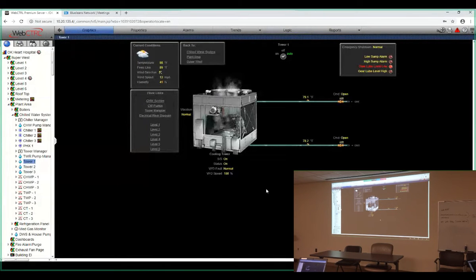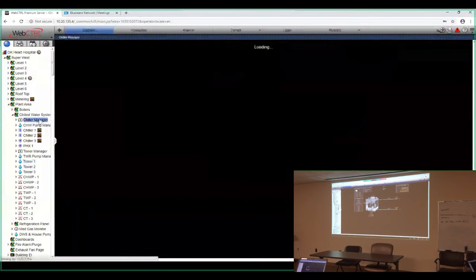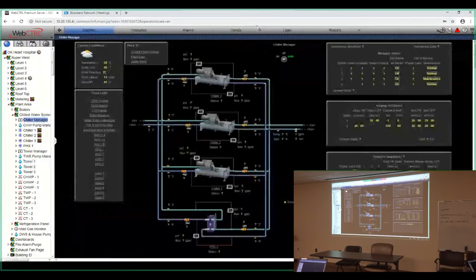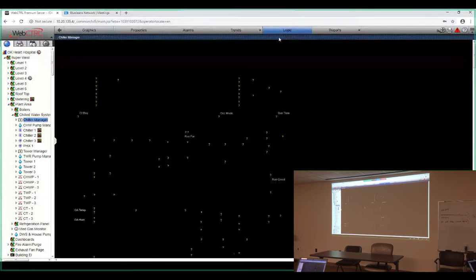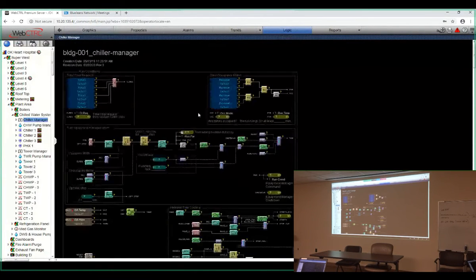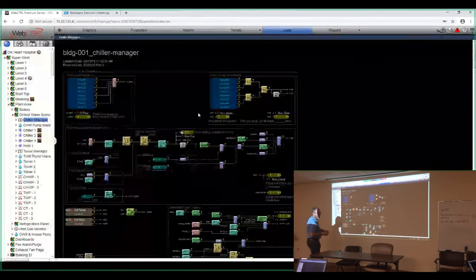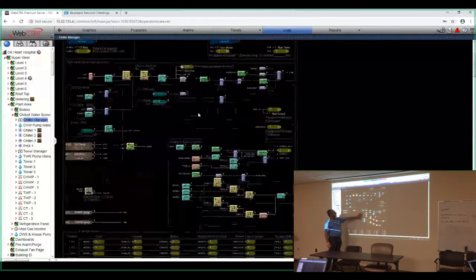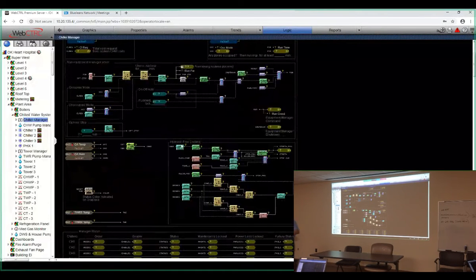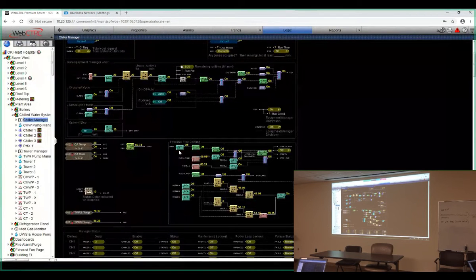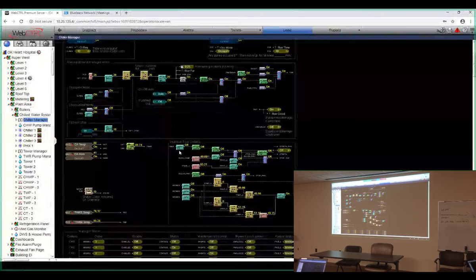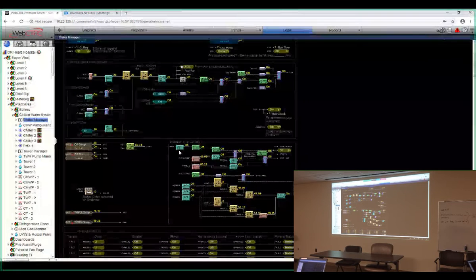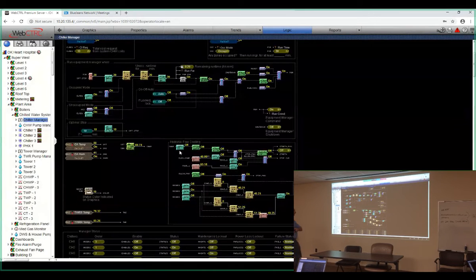All right, let's go back to chiller manager. Go to the logic for me. I want to explain to you how it goes into free cooling. I don't expect you to go through the logic, but I just want you to know what's going on. So when the outdoor temperature gets below 33 degrees for, I believe it's 20 minutes, we're going to initiate the free cooling sequence. These set points are all changeable too. These were the initial set points.